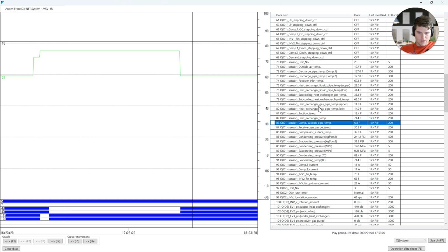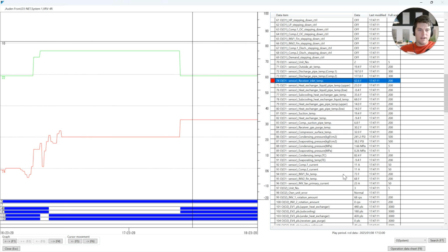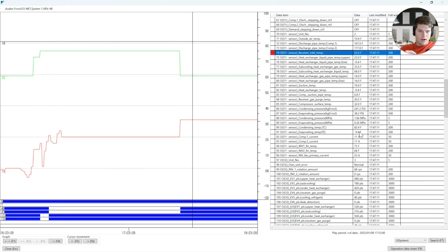This happens to me. You look at so much data that you're just staring at it, but you can't seem to find it. Inlet liquid temp here, and then we're going to go over and do our condensing temp. It's important to remember that you want to make sure you're populating the right saturation temperature and not the wrong saturation. We want saturation, which is pressure converted to temperature for that refrigerant in that location. Because we're talking liquid line, we're talking high pressure, so I go to my condensing temp.